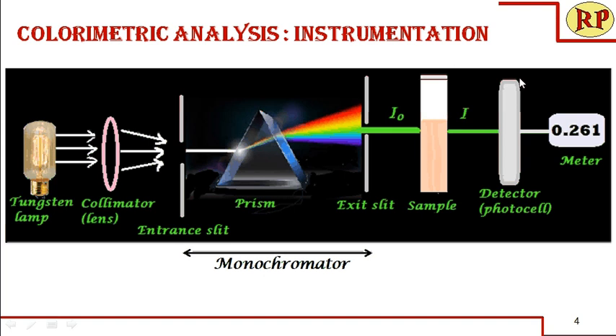We use a detector to detect the intensity of the transmitted light. A photocell is normally used, which generates current proportional to the intensity of the transmitted light. However, we do not want the transmitted light intensity — we want the absorbance. From Beer-Lambert's law, A = log(I₀/I). This instrument calculates and displays the absorbance value, though we also have the choice of selecting transmittance.